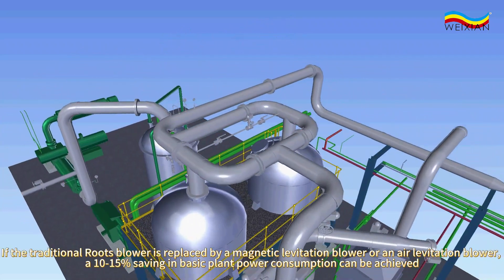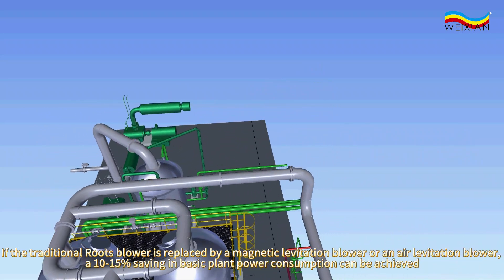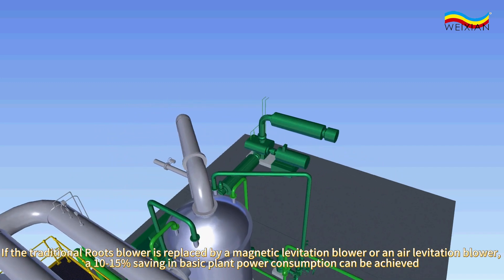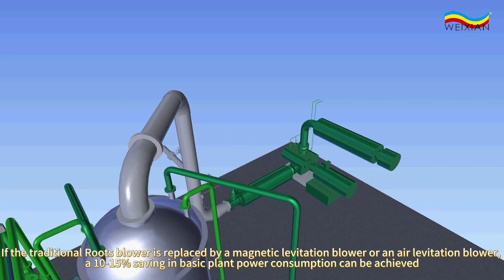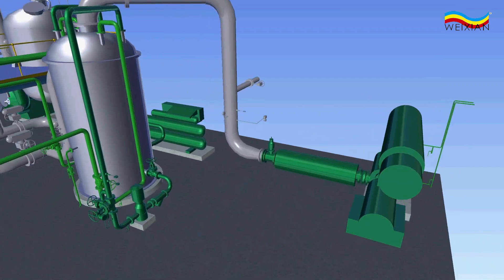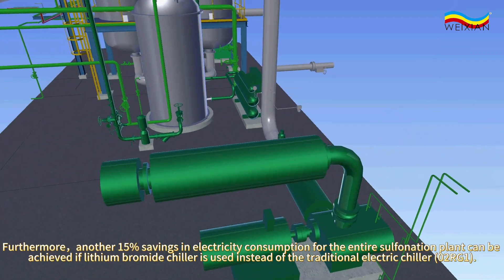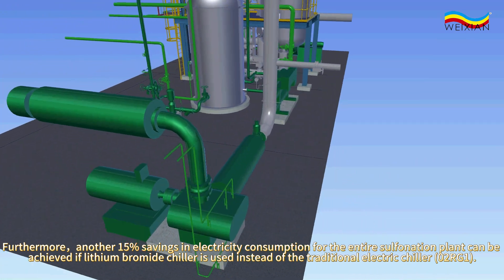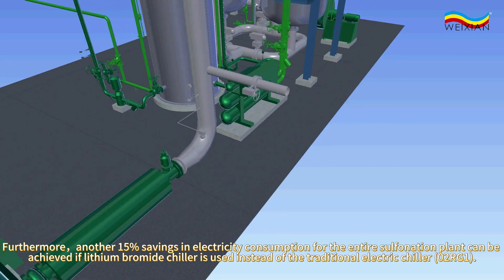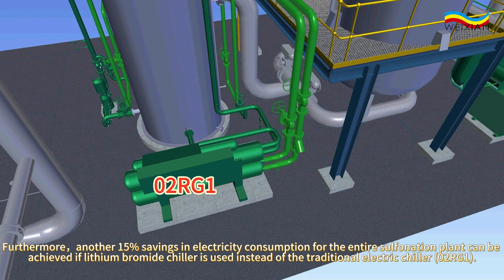If the traditional roots blower is replaced by a magnetic levitation blower or an air levitation blower, a 10% to 15% saving in basic plant power consumption can be achieved. Furthermore, another 15% savings in electricity consumption for the entire sulfonation plant can be achieved if a lithium bromide chiller, 02RG1, is used instead of the traditional electric chiller.